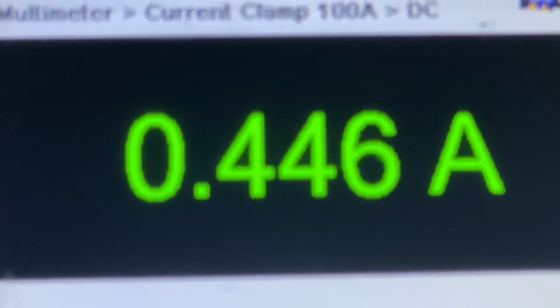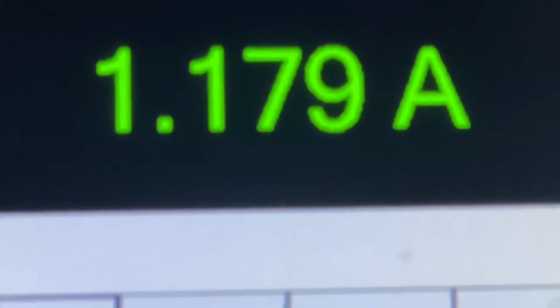Not quite sure why it's fluctuating between 0.4 and 1 amp, but that's also a very good value. If you do the math quickly on a 70 ampere-hour battery, even at 1 amp you'd be draining over about 70 hours, which would be really good.